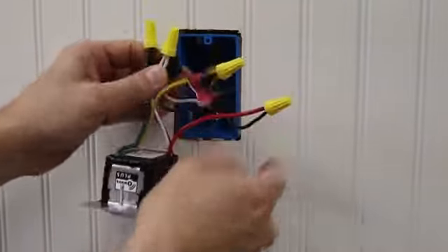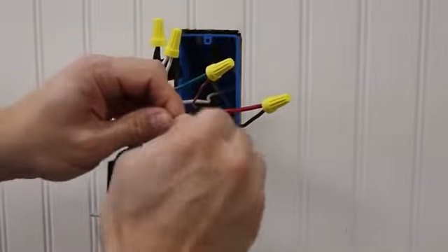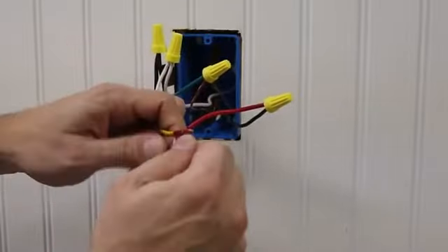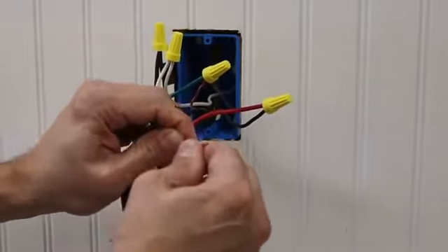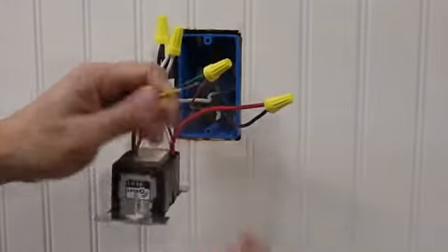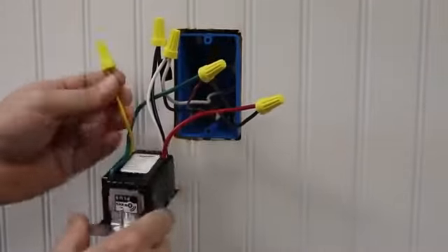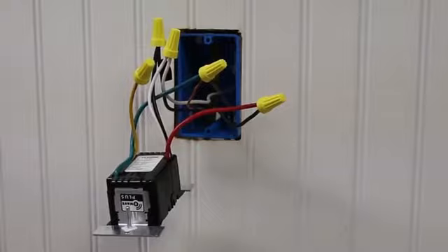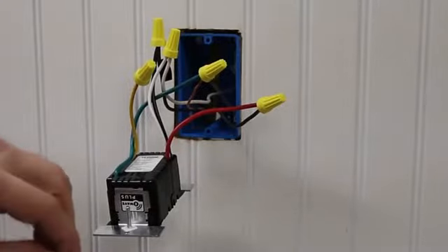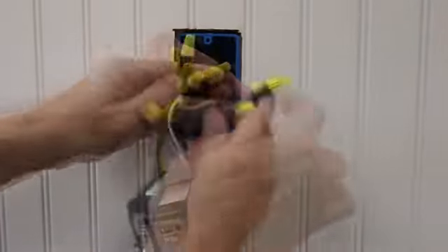Give the wires a tug to ensure they are firmly held in the wire connector. The yellow-red dimmer lead should have a red insulation affixed. If the red insulation label is not affixed, please use electrical tape or a wire connector to cover. Dress the terminated wires with electrical tape to ensure stability before the device is installed in the wall box. The device is now terminated.